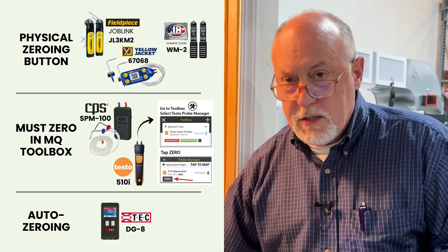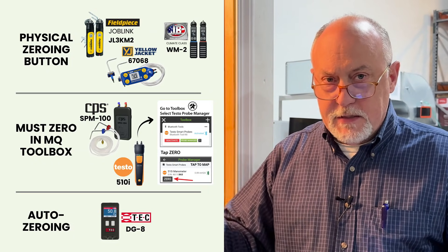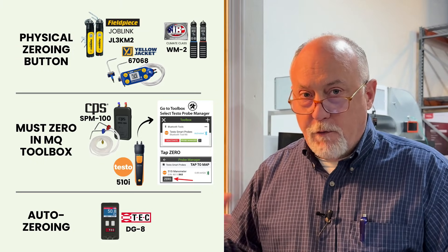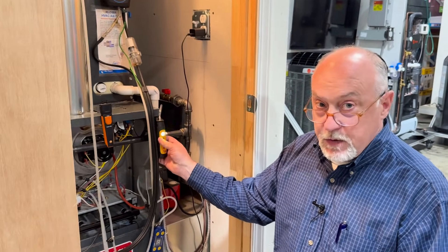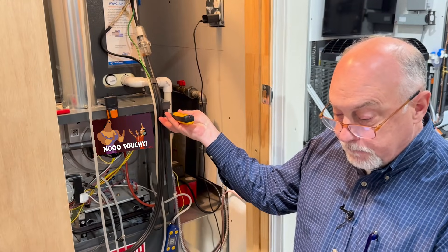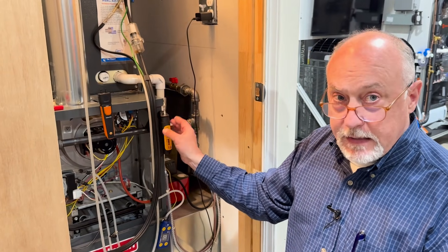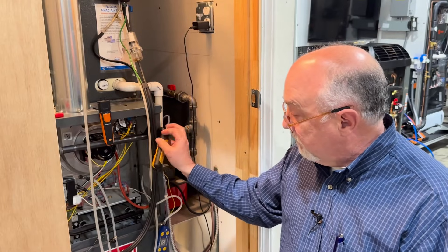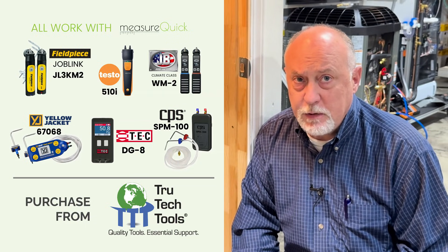Every one of these manometers has a zeroing process except for the TEC DG-8 — it auto-zeroes. You'll hear a click periodically; that clicking is it going through an auto-zero process. You do have to follow the manufacturer's directions: zero the manometer, then zero it in MeasureQuick, and going forward you just zero the manometer before you use it. Also watch the position: whatever position you zero it in is the position you want to hang it. If you change to a horizontal position it could influence the diaphragm depending on the resolution of the manometer. Zero it and keep it in the same position — and that's pretty much it. Simple to use: just pick the one you want and go to town.